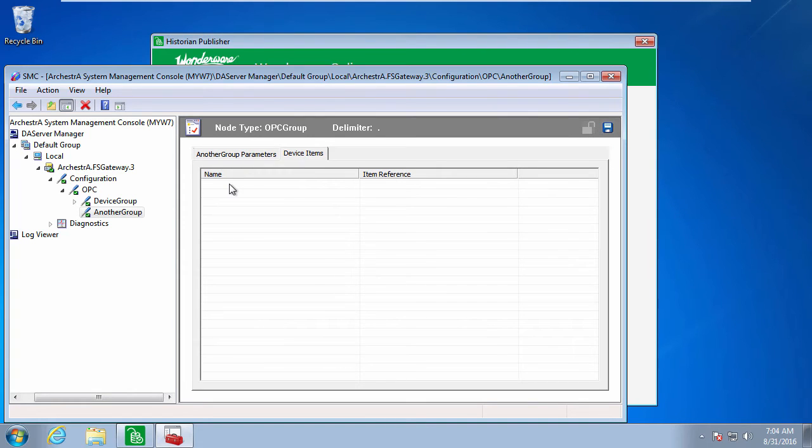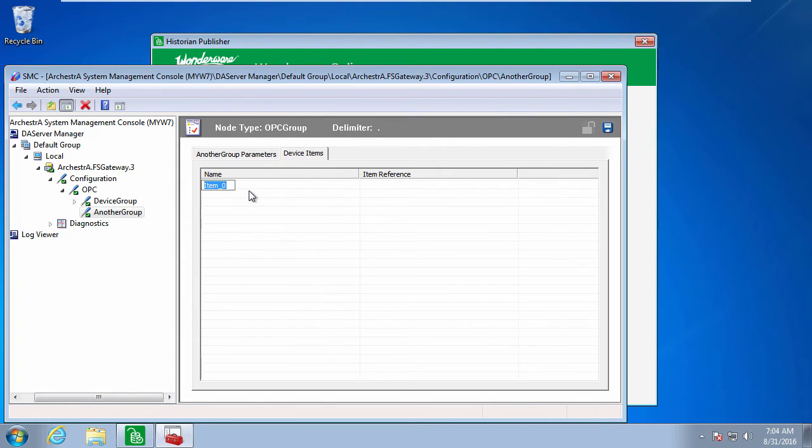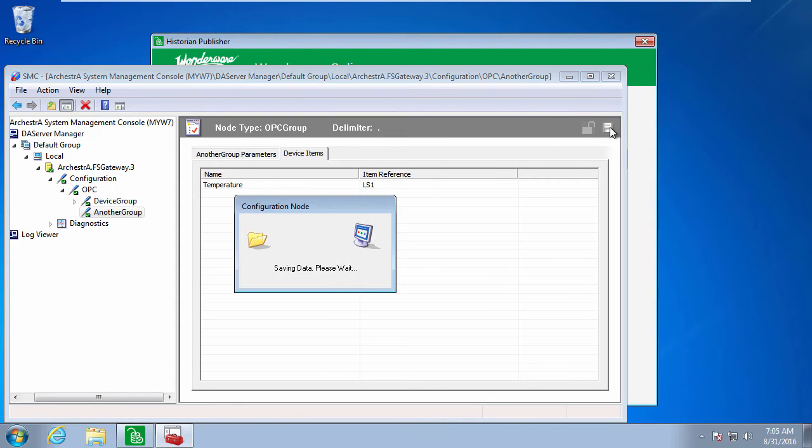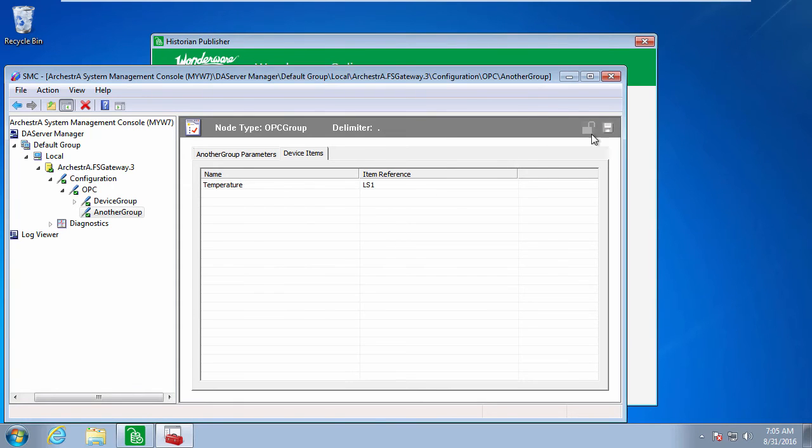I can also set up aliases. Again, these are optional, but I can give a more meaningful name for what might be a rather cryptic item name in the OPC server. So in this case, the familiar name I'll use is temperature, and that maps to LS1 in the actual OPC server.